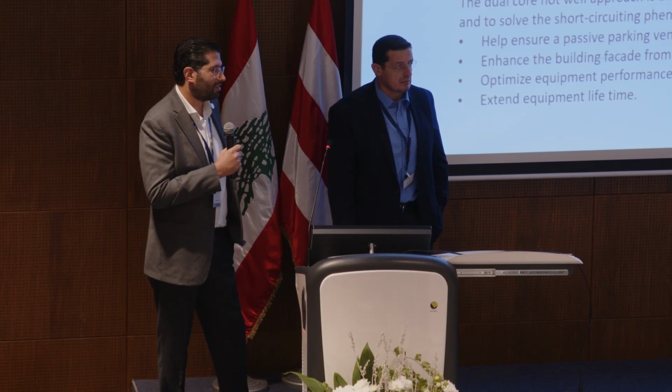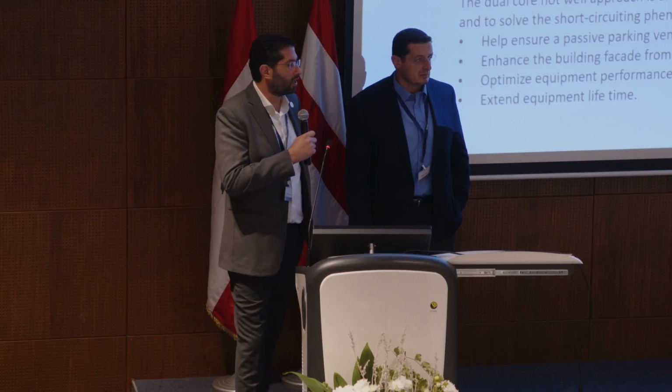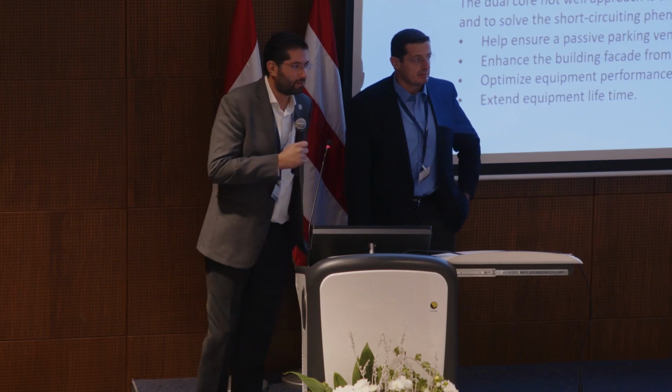I mean, I didn't really see any benefit for the parking ventilation because you still need active exhaust. You still need fans over there, exhaust fans. Need maybe jet fans to circulate, but the main 31,000 LPS for this example, we've saved on this, the fans and the operational cost of that. Basically, once you put jet fans, you don't really need ducting and the exhaust fan.